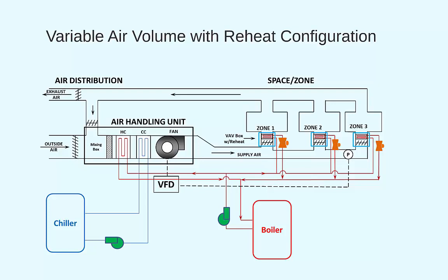The VAV with reheat configuration is shown here. These seem to be very common in the Air Force. This system should look very similar to what we just saw, only now we have brought back the boiler and hot water loop and installed reheat coils in our VAV boxes. So our VAV boxes now have two items in them: the damper, which has the ability to modulate, and a reheat coil, which has a control valve which can modulate the flow going through it.